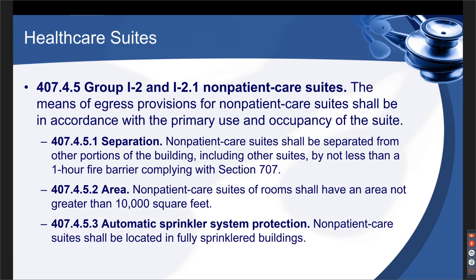407.4.5 is a new section to the 2022 code that talks about non-patient care suites. And this is something that is sort of outside of the definition found in Chapter 2 for suites, which allows administrative areas to be considered non-patient care suites. So this provision would apply, and the limitations are pretty limited. Basically, it has to be separated from other portions of the building by that same 1-hour fire barrier. The suite can be 10,000 square feet and has to be fully sprinklered, but basically that's the extent of the requirements.